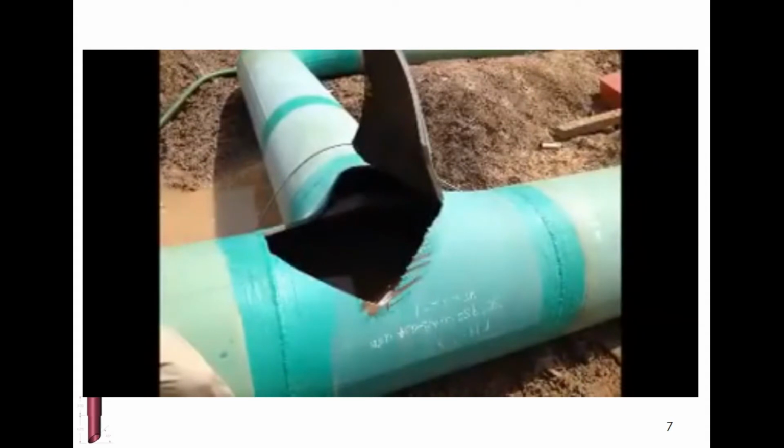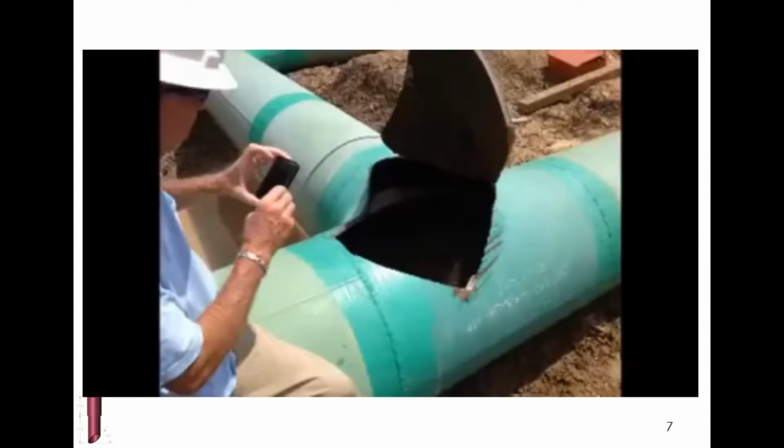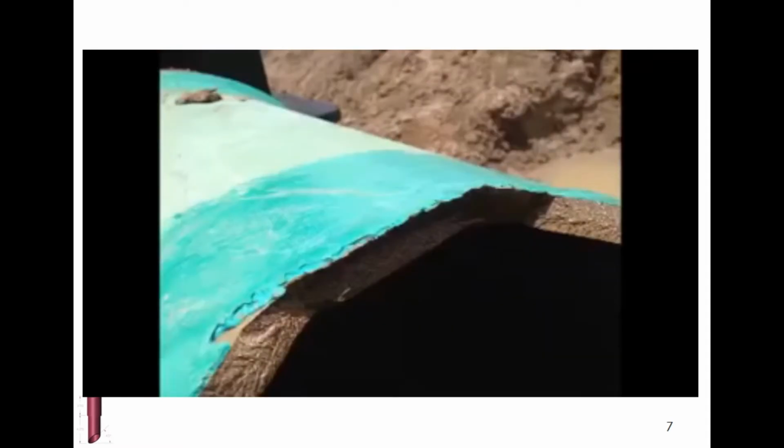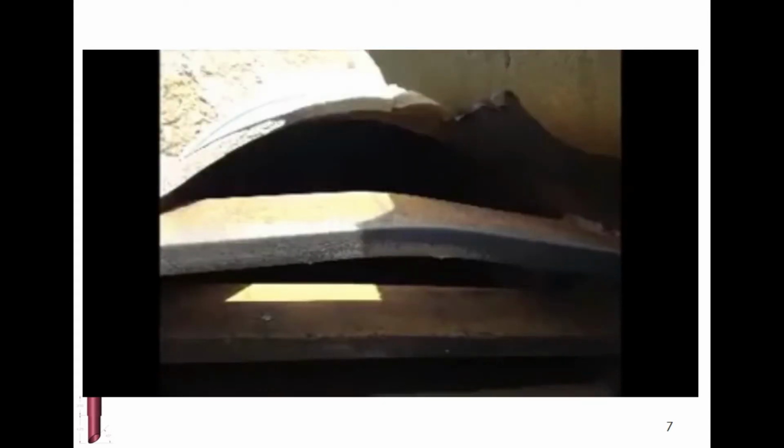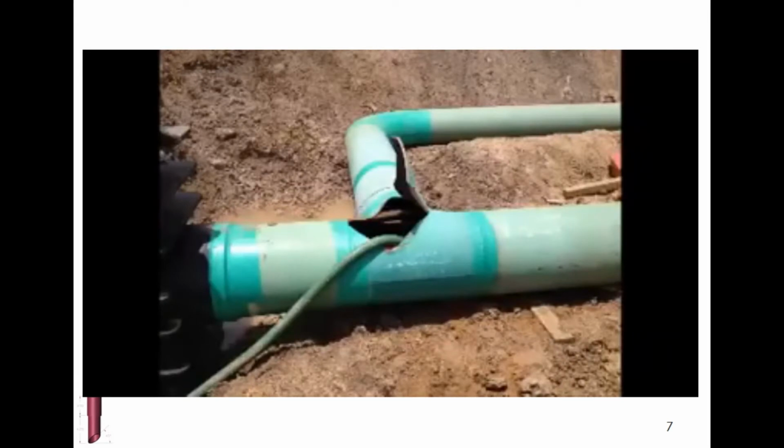We're looking at 3/8 inch wall thickness pipe that just peeled back. I think there's a 26-inch line, and it's standard wall. So you're seeing a lot of mass, a lot of metal mass ripped away. That's a lot of force that took place in that piece of pipe. Especially when you think the pipe is curved, so they had to overcome the resistance to bending of that curve.